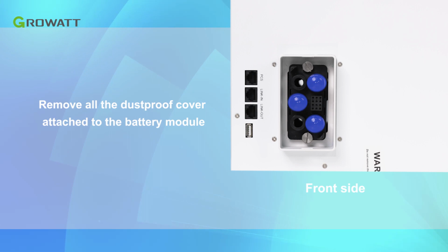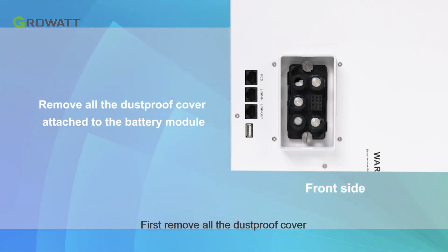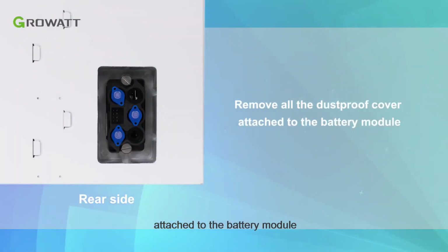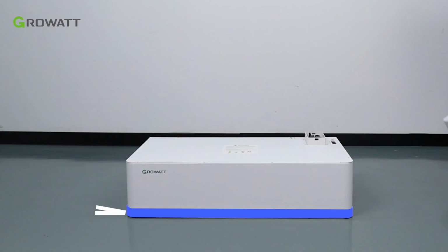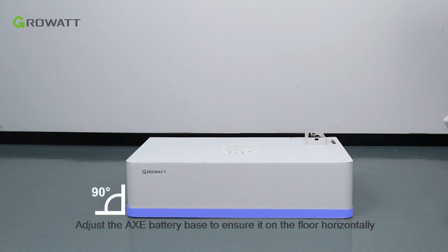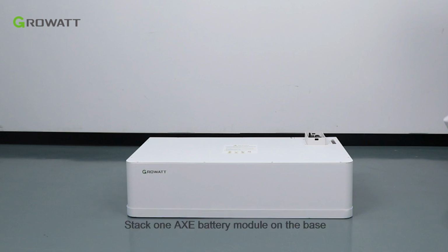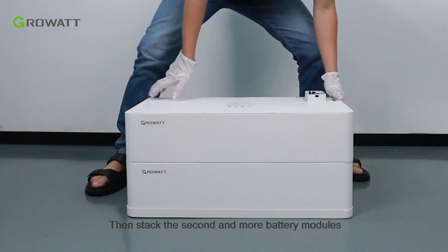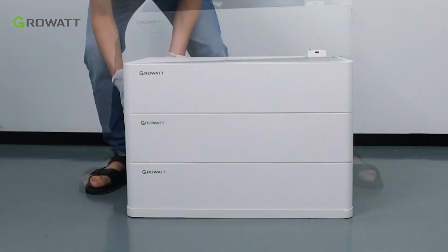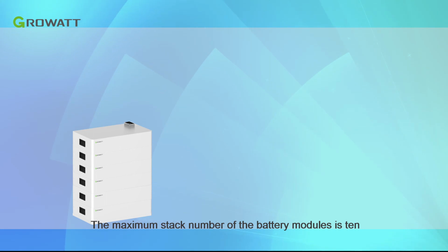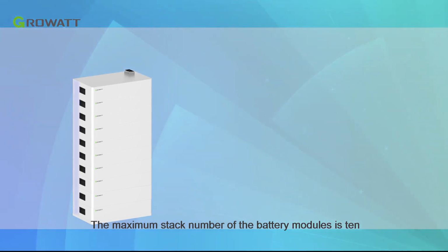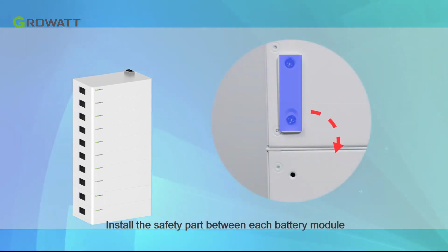AXE battery installation. First, remove all the dust-proof covers attached to the battery module. Adjust the AXE battery base to ensure it sits on the floor horizontally. Stack one AXE battery module on the base, then stack the second and more battery modules. The maximum stack number of the battery modules is 10. Install the safety part between each battery module.